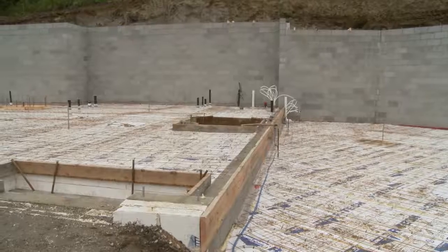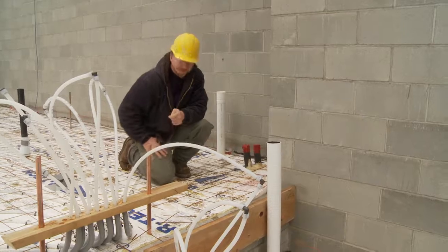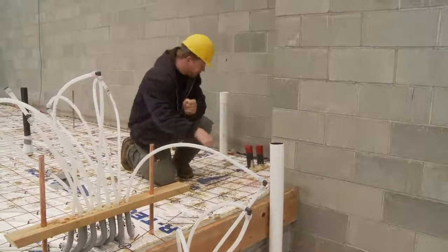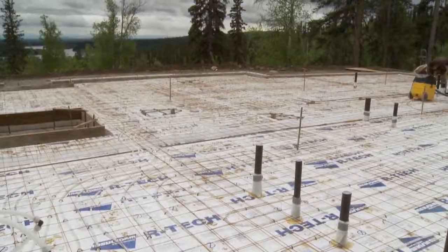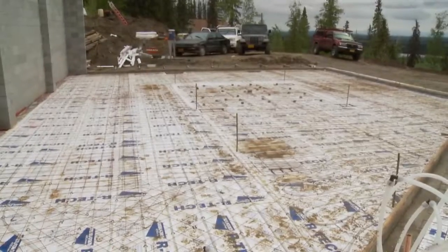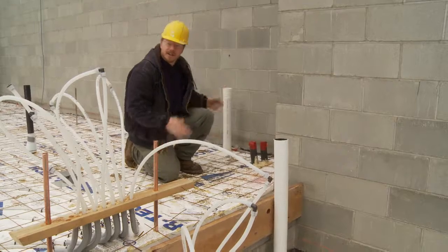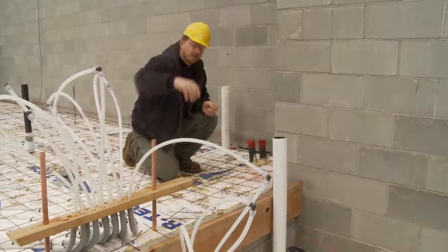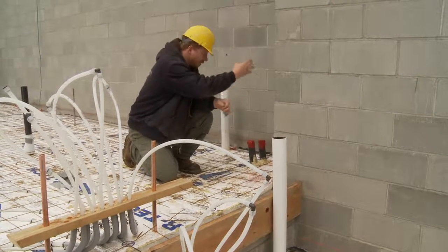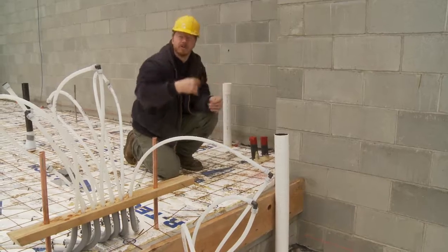This house has a stepped floor system with a concrete bearing wall dividing the floor in half. Since the tubing couldn't be run through the floors, we've got two separate runs of tubing — a loop running around the perimeter of the upper floor and the same run of tubing running around the lower floor. The lower floor system meets at a collection point here, the upper floor meets here. The runs of tubing are divided roughly in half, and the radon fan will connect to both pipes in a riser, drawing roughly equally from both floor systems.